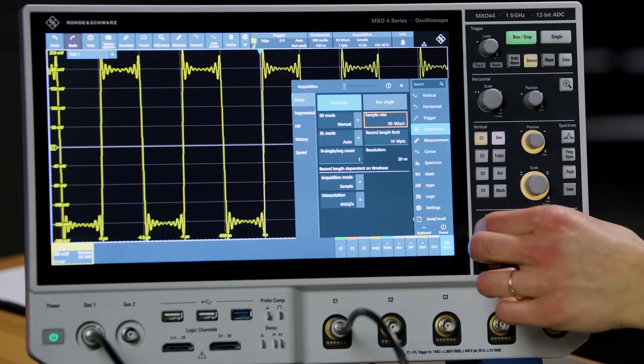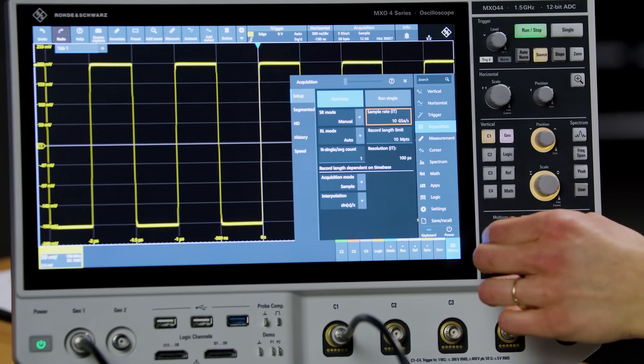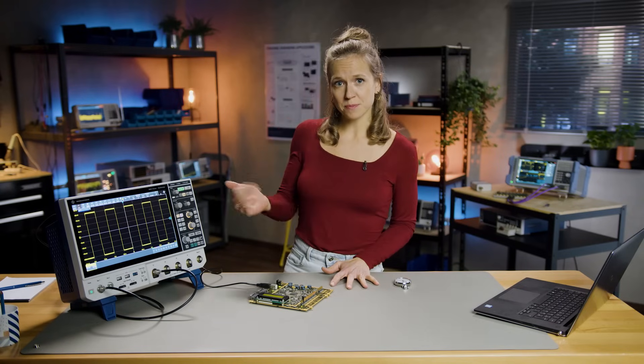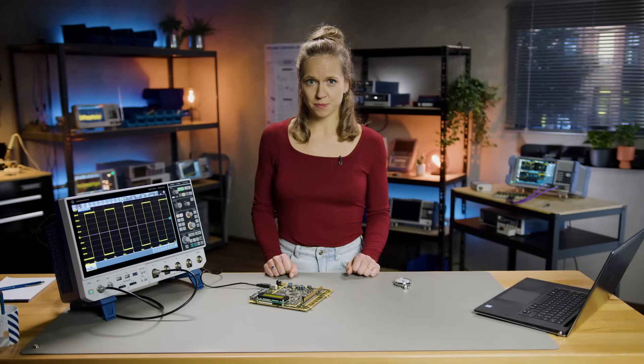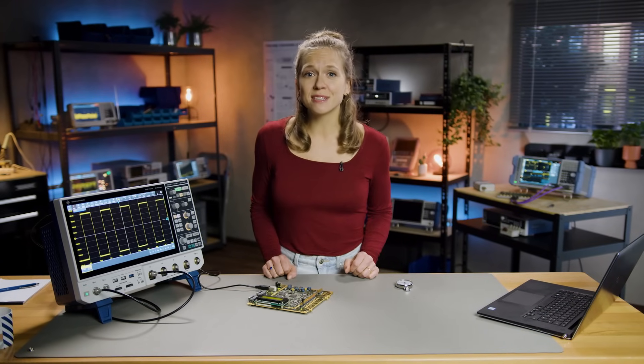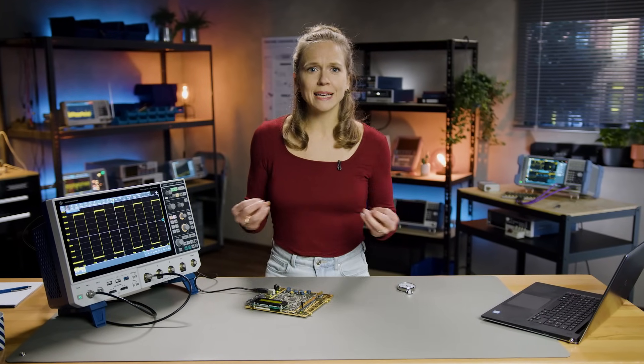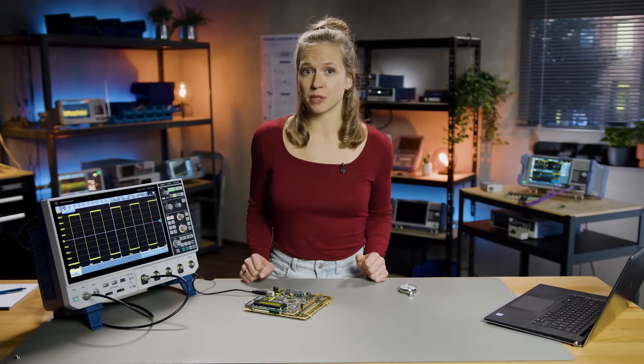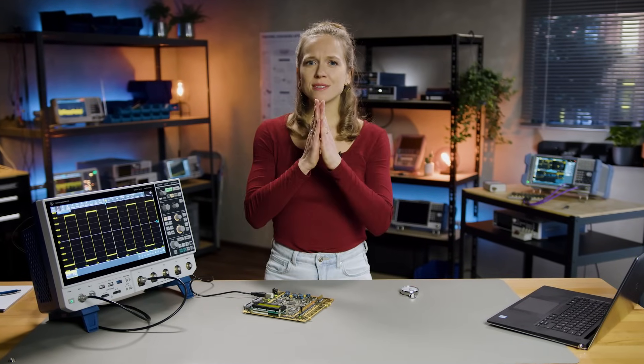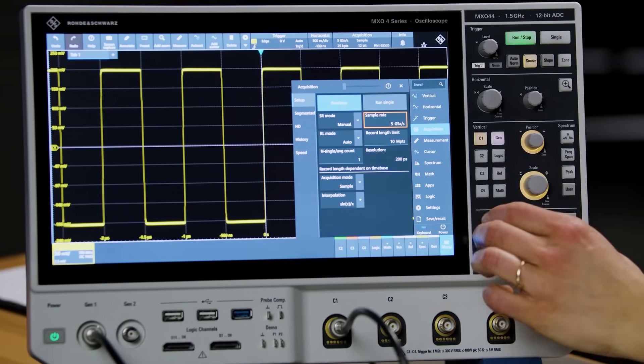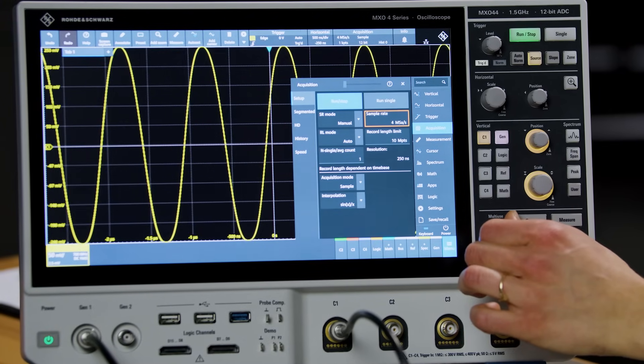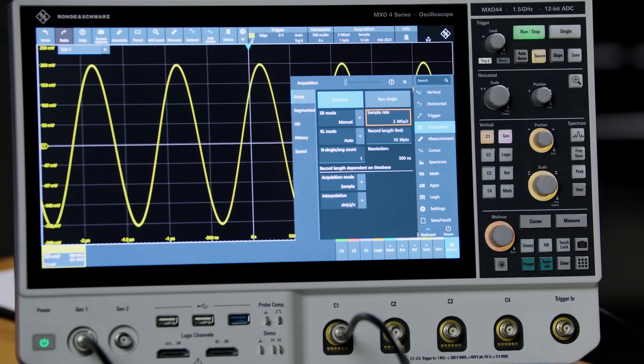These sampled values of the waveform are stored in the instrument's memory, which in the end is what we see on the display. You're probably wondering which sample rate to choose. High enough to be accurate is the decisive factor here. This is because if the input signal is sampled too slowly, we will not get an accurate representation of the real signal. We call this aliasing. Notice what happens to the captured data when we lower the sample rate from gigasamples per second to a few megasamples per second. What should be a square is now a mere sine wave.